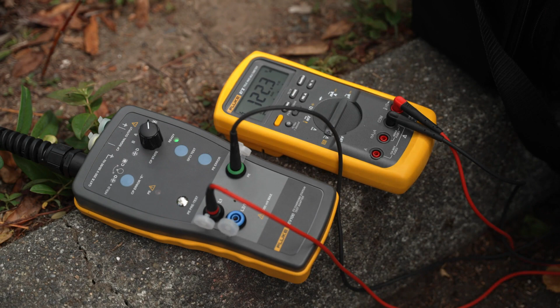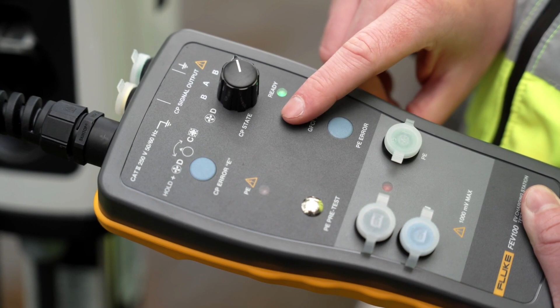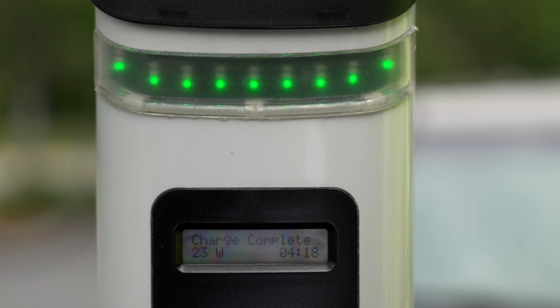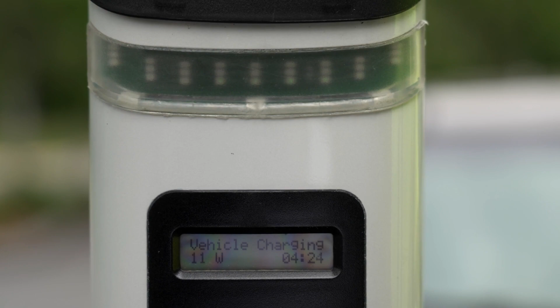Simulate errors like an interruption of the protective earth system using the PE error button. The voltage supply is cut off and then restored. You will see this indicated by a colored light on most charging stations. Test the station's GFCI system with the GFCI testing function. Once the green ready indicator is lit and the station is in state C, press the GFCI test button. The charging station will display an error and will terminate the voltage transmission. This will verify that the GFCI is operating properly for protection against electric shock.